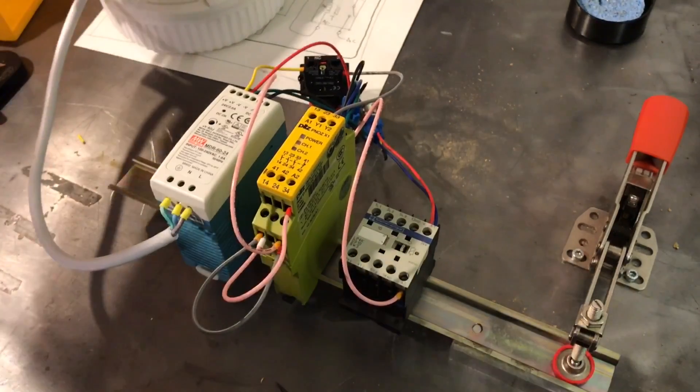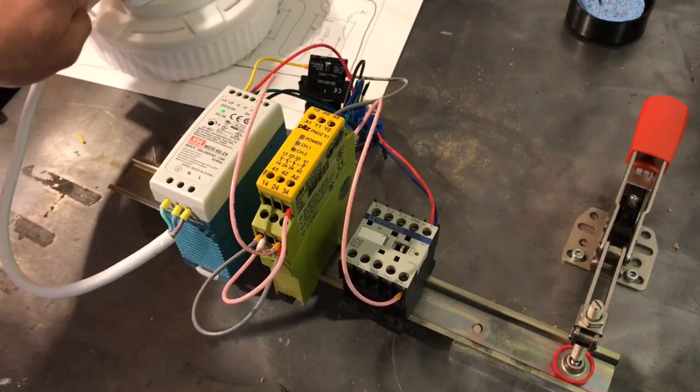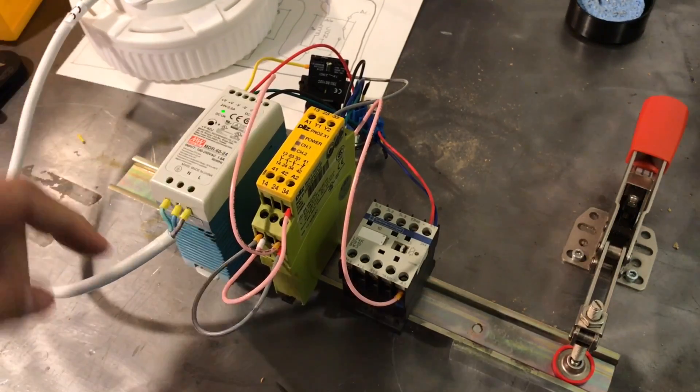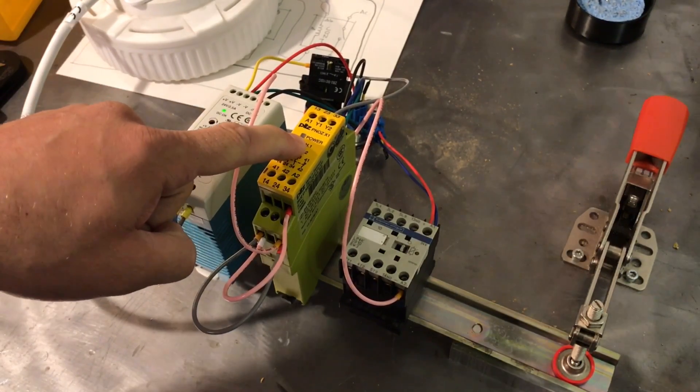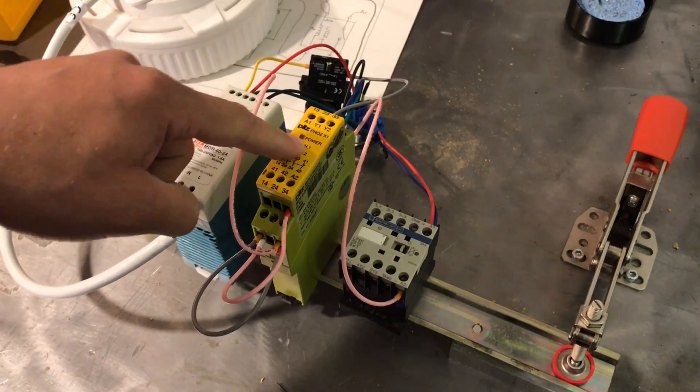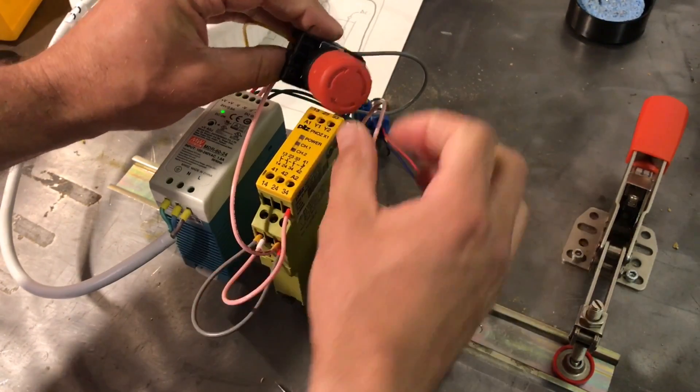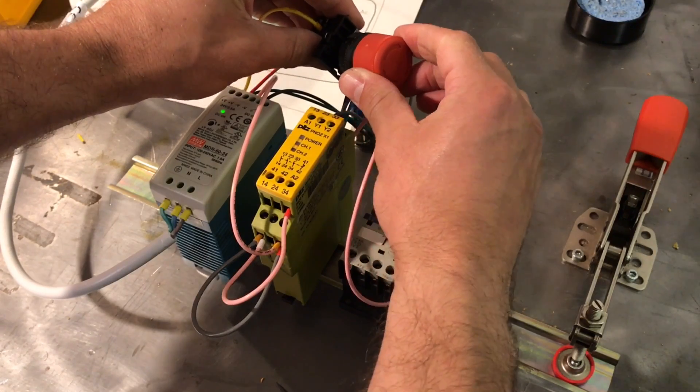Plugged it in, DC lights come on, but we have no power to the Pilz. That's because the e-stop is currently depressed.